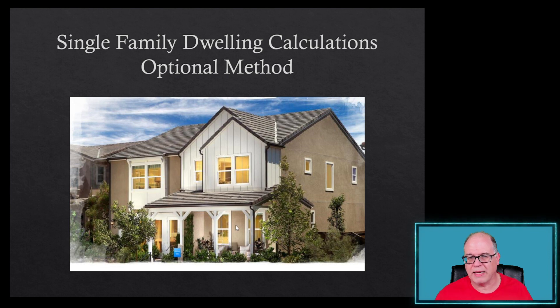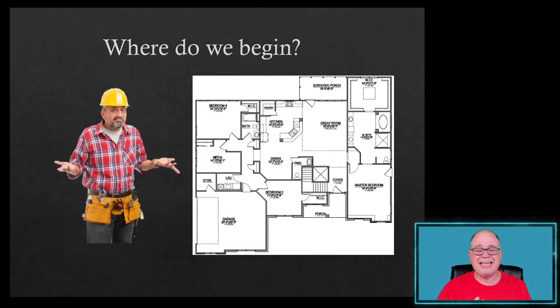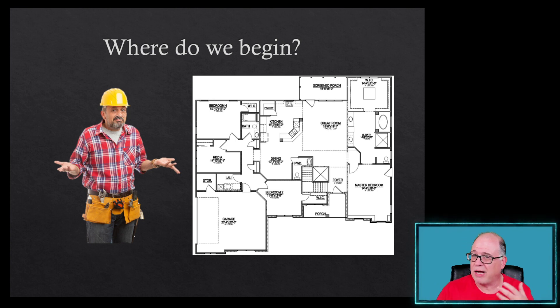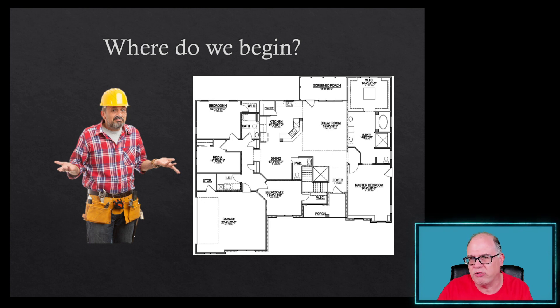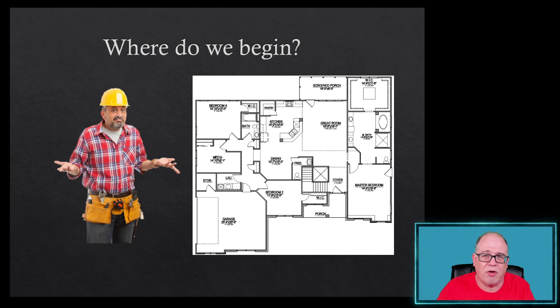Here's our dwelling — probably a familiar one if you were in the series where we did the standard method. Where do we start? Like any calculation for service, we have to know what's going into the dwelling. We need to know what the appliances are, how many small appliance branch circuits we're going to have, how many laundry circuits we're going to have, the outside dimensions, and what needs to be excluded — open porches, garages, attic space not adaptable for future use. You're the electrician; you need to compile this information from the general contractor or the owner.